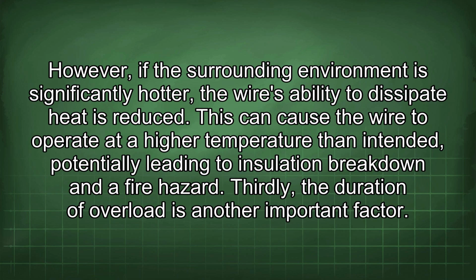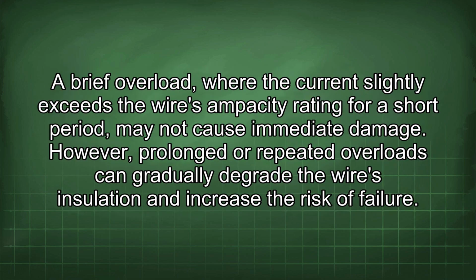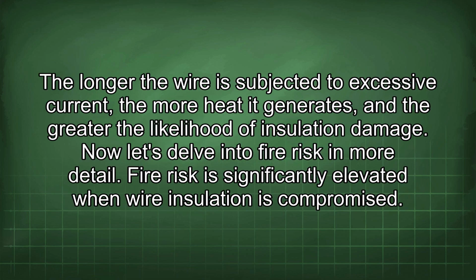Thirdly, the duration of overload is another important factor. A brief overload, where the current slightly exceeds the wire's ampacity rating for a short period, may not cause immediate damage. However, prolonged or repeated overloads can gradually degrade the wire's insulation and increase the risk of failure. The longer the wire is subjected to excessive current, the more heat it generates, and the greater the likelihood of insulation damage. Now let's delve into fire risk in more detail.